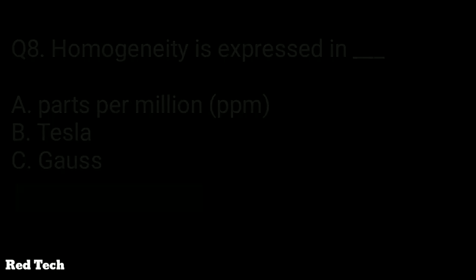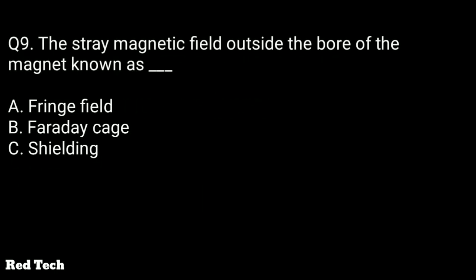Question number nine: the stray magnetic field outside the bore of the magnet is known as — the options are fringe field, Faraday cage, or shielding. The right answer is fringe field. This is basically the stray field that crosses conventional walls, floor, or ceiling, and is potentially harmful to patients with pacemakers or monitoring devices.